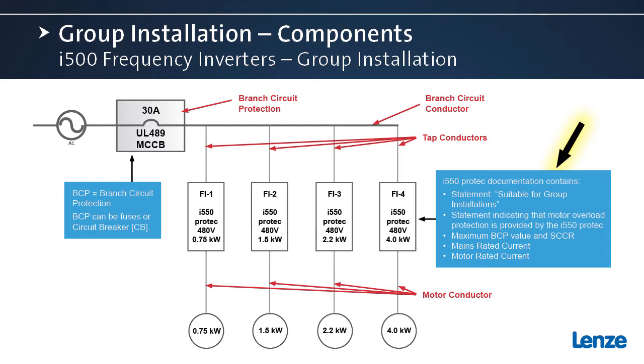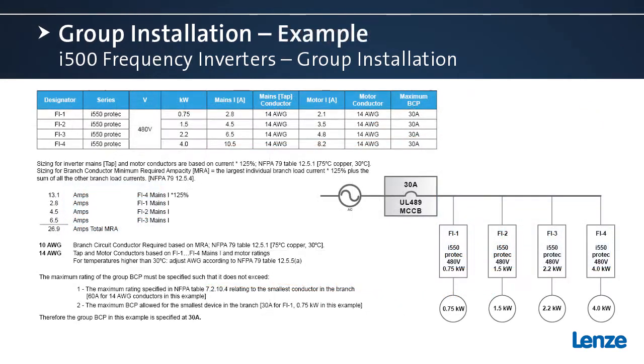All our documentation completely complies with the requirements of the NFPA 70 and the NFPA 79. Here's an example of an NFPA 79 compliant group installation system. You can see on the slide here, throughout the slide, I've referenced the relevant NFPA 79 tables and sections where they apply.